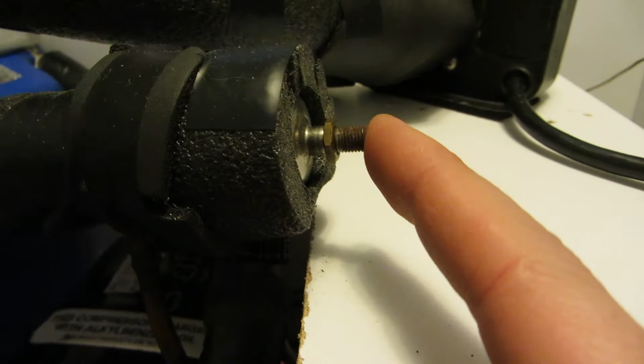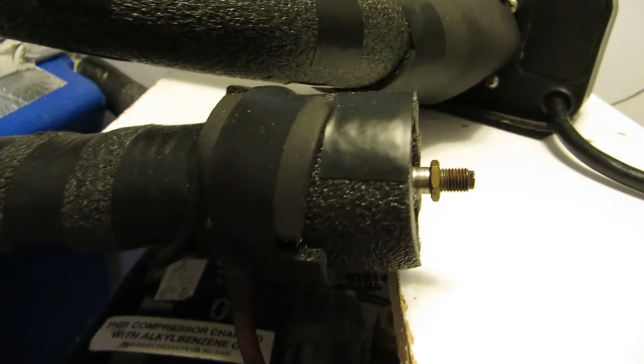It's been years since I heard this term - I think this is a CPEV valve, constant pressure expansion valve. It's not like a TX valve with a bulb that can open and close based on the loads. This here has a set screw on the back of it - you set it to the pressure you want and it will stay at that pressure no matter what the load is.